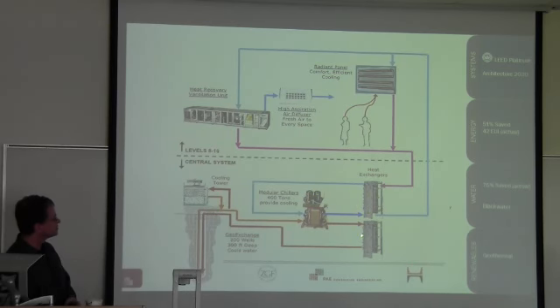We take it through heat exchangers because the Port really didn't want to take any undue risk with bringing water in. We considered that possibly if there needed to be more capacity in the future, we could run a glycol solution in part of this loop. So they didn't want to have glycol up in the office space from a hazardous material standpoint. Also, there's a height difference. This building, think about it, it's 340 feet down and it's 10 stories up. So there was some concern about reaching the maximum pressure at the bottom of the well with the material for the piping.